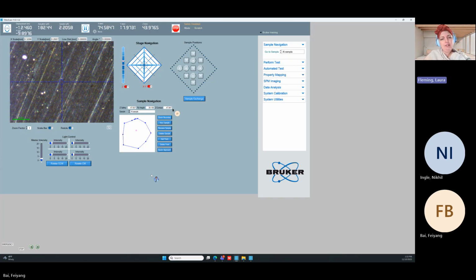If you do not have this Z contact height, if it is 0, the system is unsure where the sample height really is. So it starts the slow approach all the way up here. And then it goes click, click, click, click, click, one at a time, very slowly until it finds the sample surface, because it doesn't want to leave any plastic deformation. That's what was happening to us. And it takes a very long time.